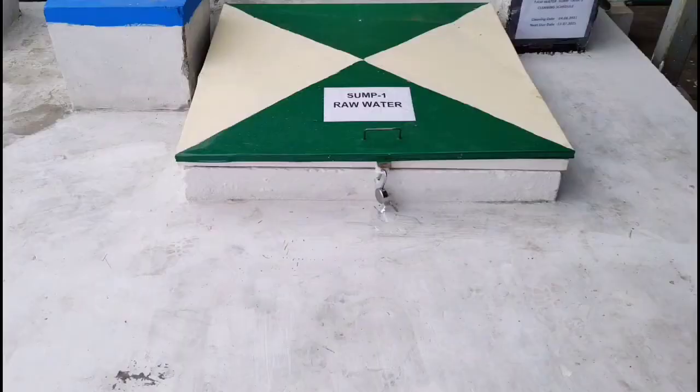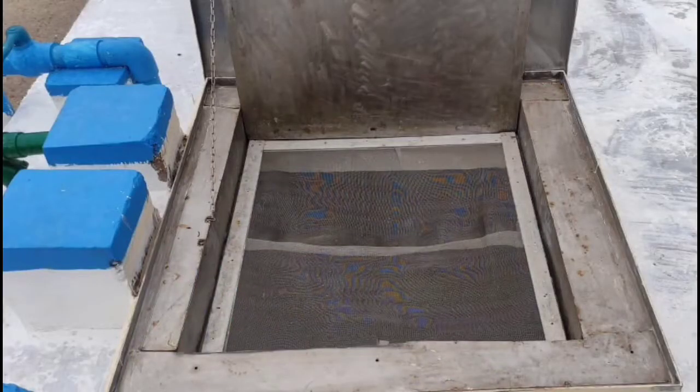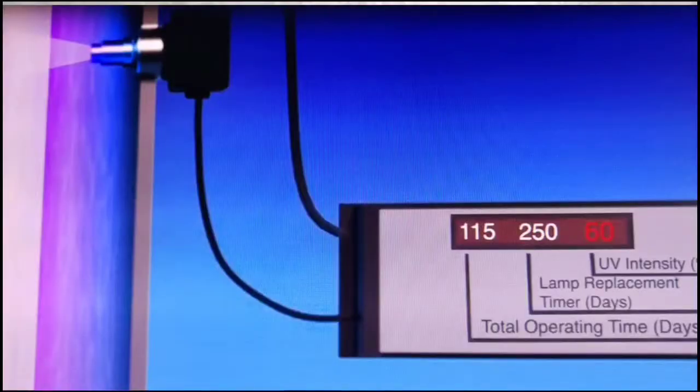Sometimes the chlorine ppm may vary, or the water may remain stagnant for several hours in the overhead tank, so the chlorine concentration will get diluted. Also, the sump tank and overhead tank doors should be closed. If opened, exposure to pests, lizard droppings, or bird droppings can introduce Salmonella bacteria. So after chlorine disinfection, the water should again pass through UV disinfection. We should keenly monitor those things.